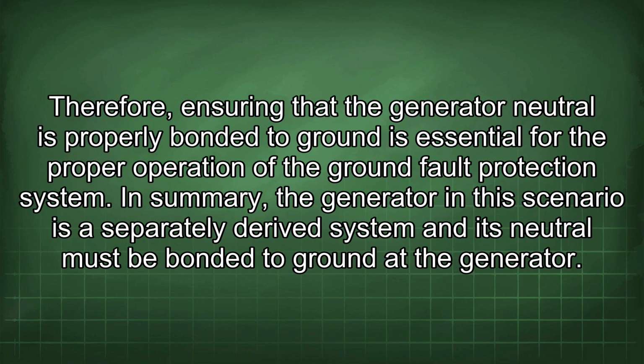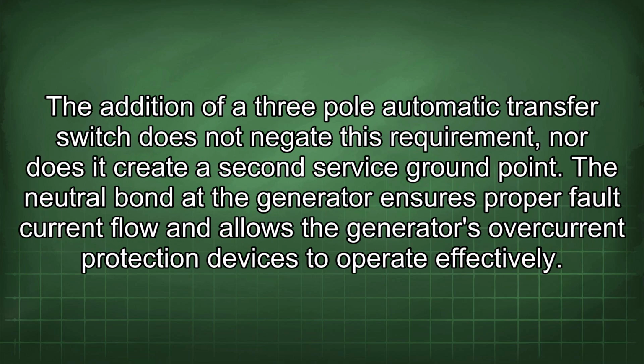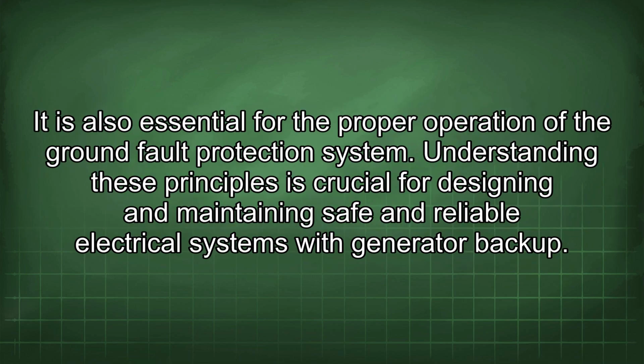Therefore, ensuring that the generator neutral is properly bonded to ground is essential for the proper operation of the ground fault protection system. In summary, the generator in this scenario is a separately derived system and its neutral must be bonded to ground at the generator. The addition of a 3-pole automatic transfer switch does not negate this requirement, nor does it create a second service ground point. The neutral bond at the generator ensures proper fault current flow and allows the overcurrent protection devices to operate effectively. It is also essential for the proper operation of the ground fault protection system.